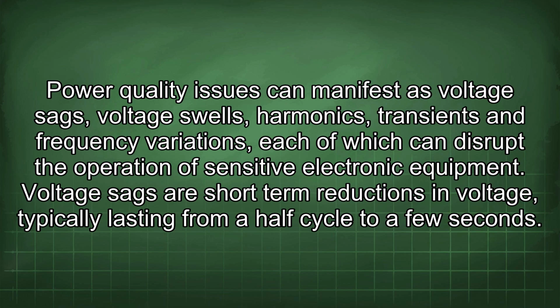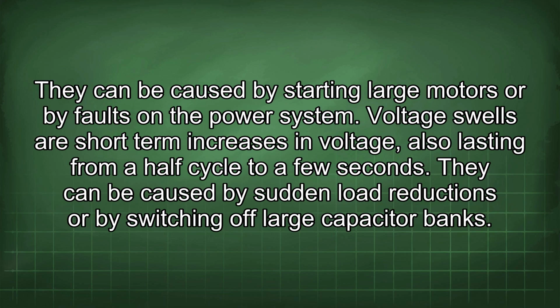Voltage sags are short-term reductions in voltage, typically lasting from a half cycle to a few seconds. They can be caused by starting large motors or by faults in the power system. Voltage swells are short-term increases in voltage, also lasting from a half cycle to a few seconds. They can be caused by sudden load reductions or by switching off large capacitor banks.